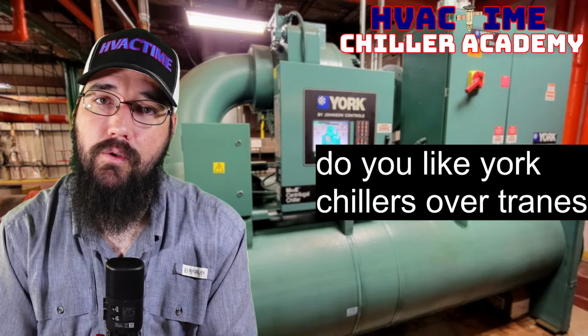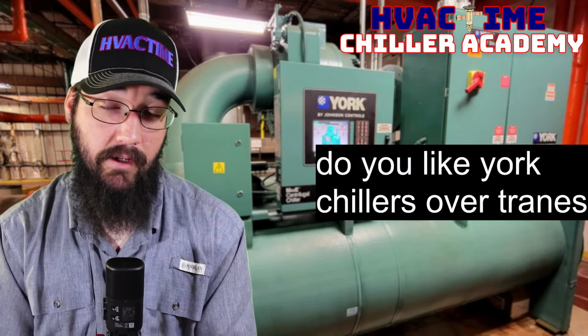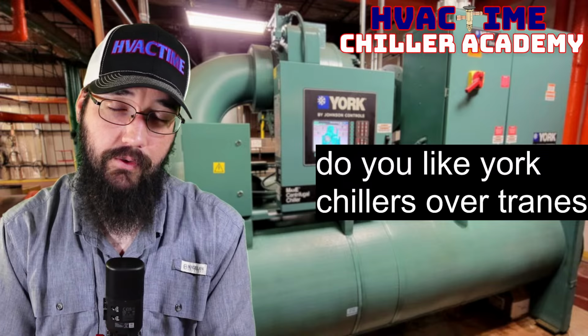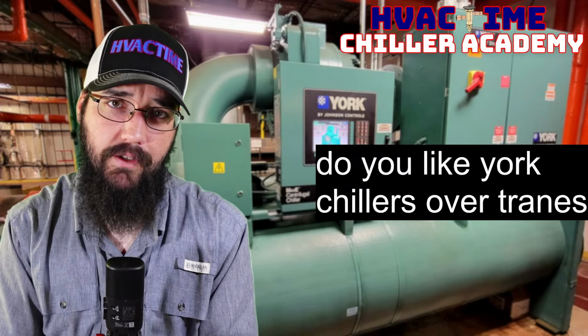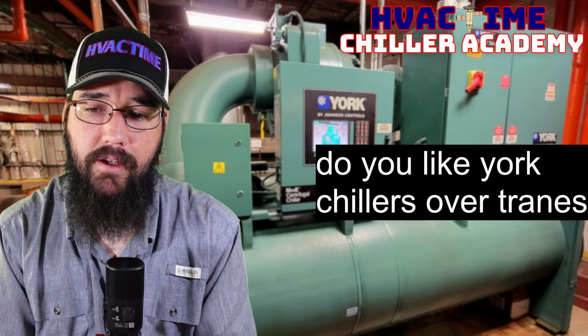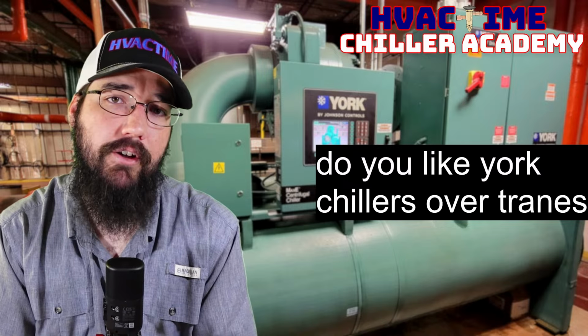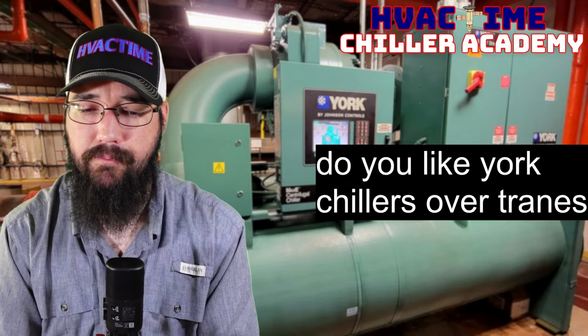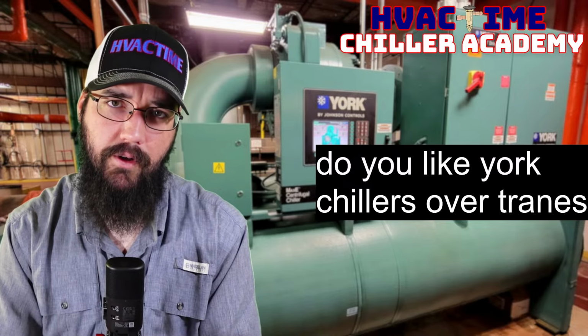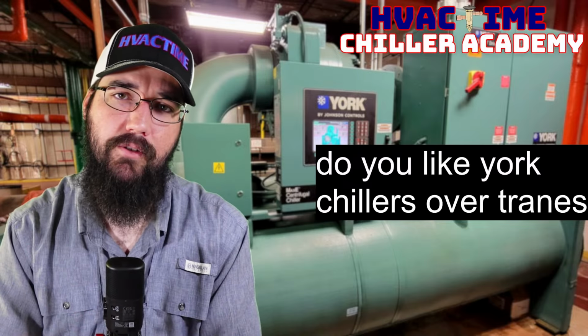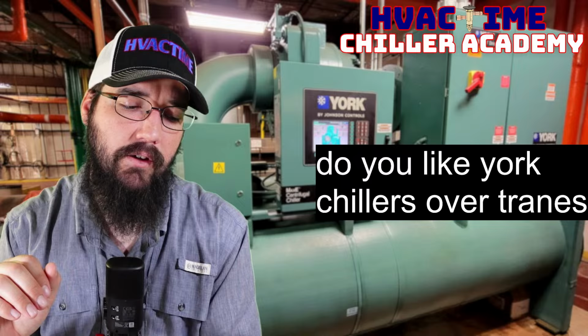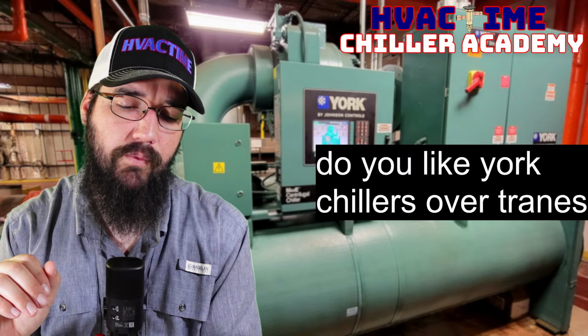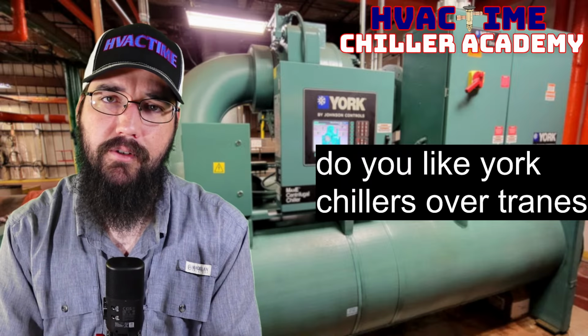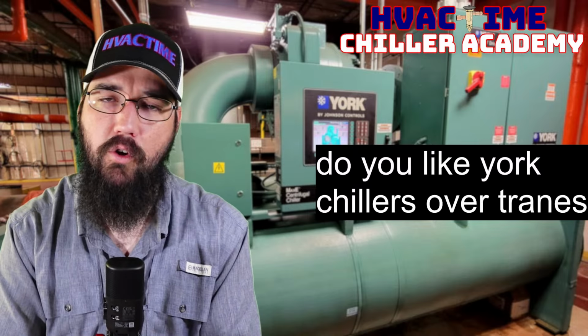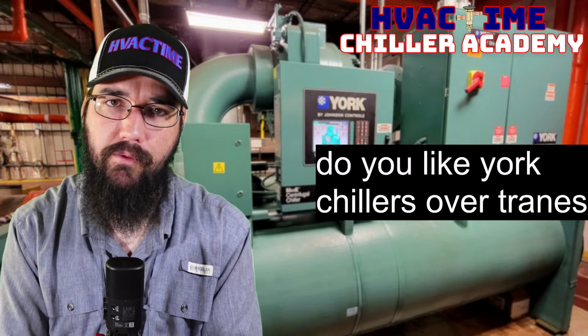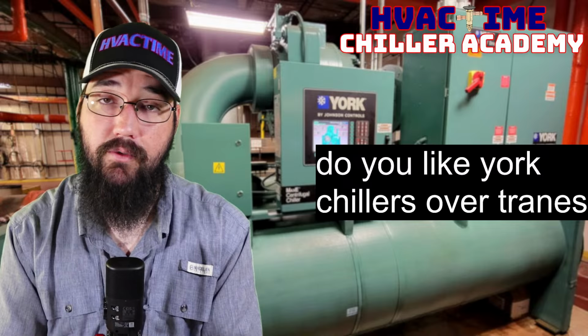That's one of the struggles with a single stage high-speed impeller versus Trane using their multi-stage low-speed impellers, right? That's just some of the engineering trade-offs that you end up having there. So in short, it comes back to application and just what you're trying to accomplish, whether or not you want to go low pressure, high pressure, refrigerant system. That's going to change whether or not you want to.